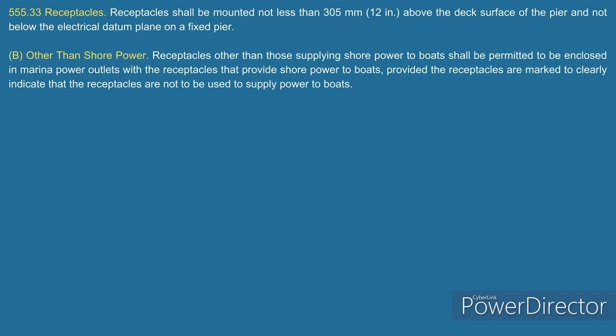This one is where they come in. They say other than shore power. It says receptacles other than those supplying shore power to boats shall be permitted to be enclosed in marina power outlets with the receptacles that provide shore power to the boats, provided the receptacles are marked to clearly indicate that the receptacles are not to be used to supply power to boats. How much more clear can this be? When you look at the heading, it's specifically telling you receptacles. And the reason they're saying receptacles is because the receptacles are being mounted in the receptacle outlet. It's not at the end of the equipment.